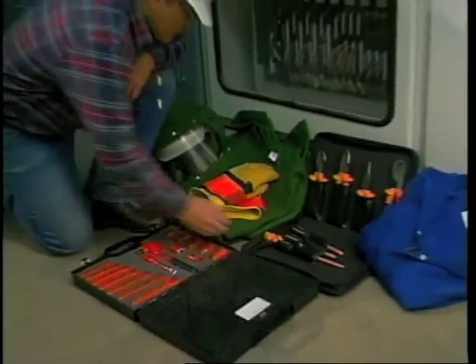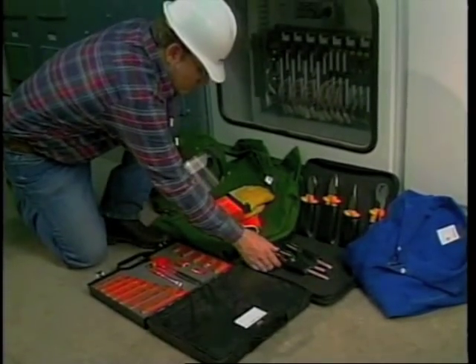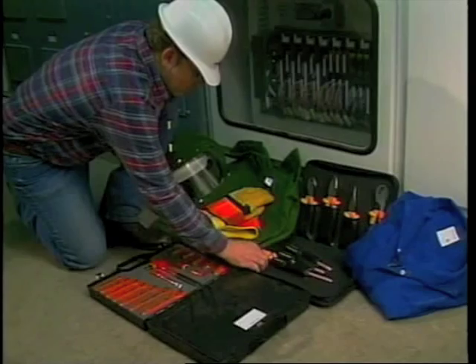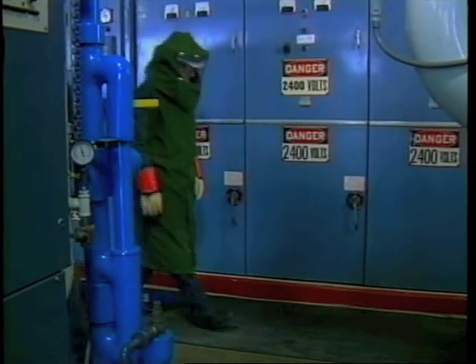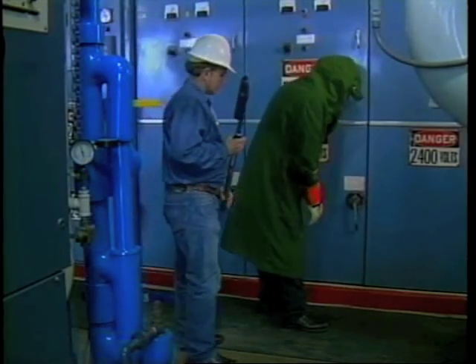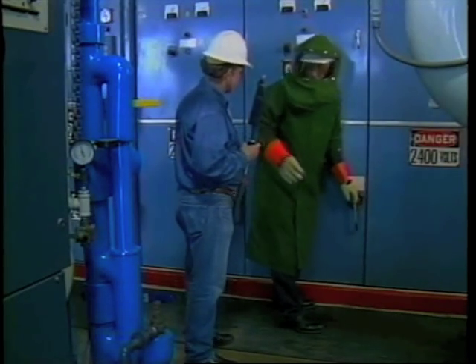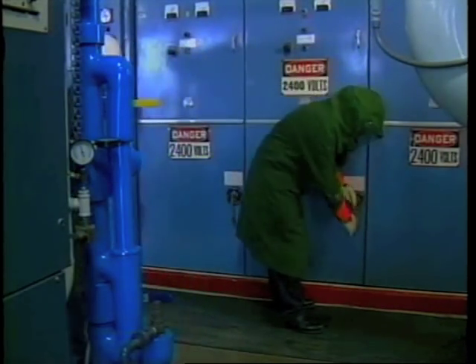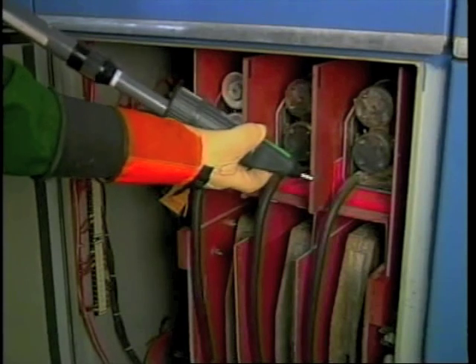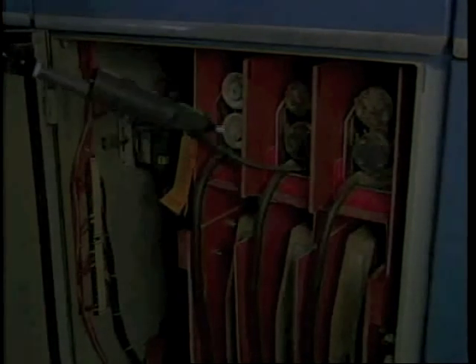Have all tools and personal protective equipment available and on site before work is begun. Open circuit breakers, fused switches, and contactors before removing or replacing them. Be sure fuses are de-energized before pulling or replacing them.